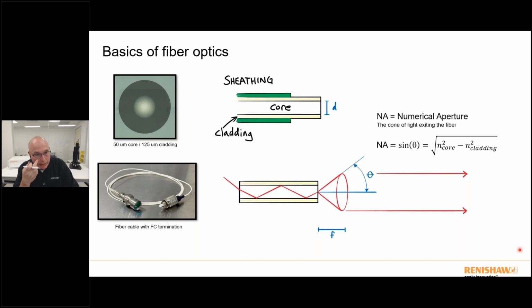So getting into fiber optics, I snapped these pictures yesterday, actually this one this morning. This is a basic fiber optic patch cable that we have, and if you look at the FC termination here, this is what the fiber looks like. The fibers themselves have a core, and that core in this image is a 50 micron core with 125 micron cladding around it. The core diameter is something that's important to understand when you're using fiber optics and developing fiber optic probes. And I'll get into the reason why that is important in a second here.